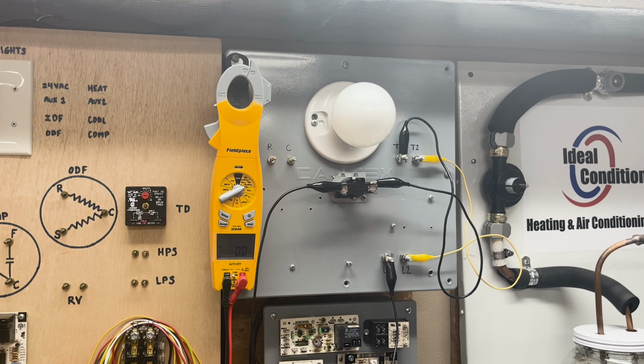One thing I want to go over with you is when these things stick, you want to know how long, if I remove 24 volts, should that relay stay engaged? Because when these relays typically fail, they fail in the closed position, which means the load does not shut off. Sometimes they do fail in the open position where the load doesn't come on. But if you're using this relay for a set of heat strips, you may experience your heat strips running if the relay has failed in the closed position, the sticking there.